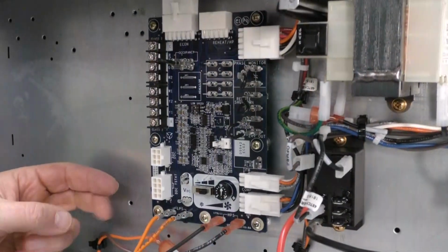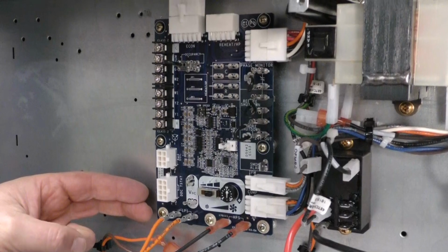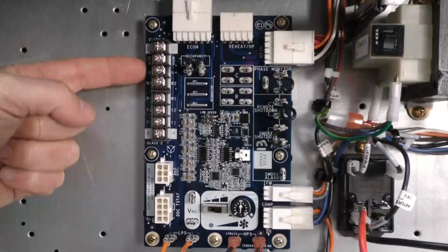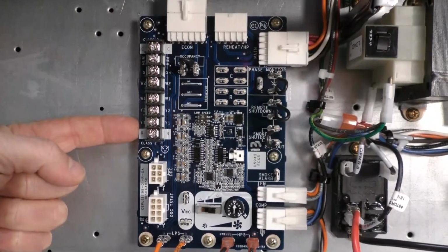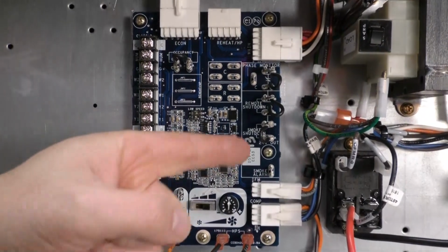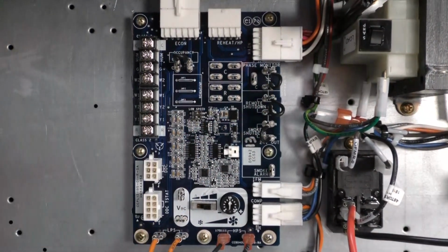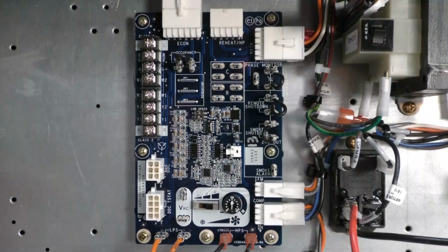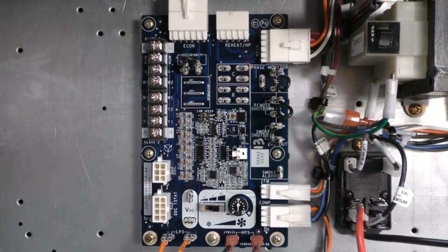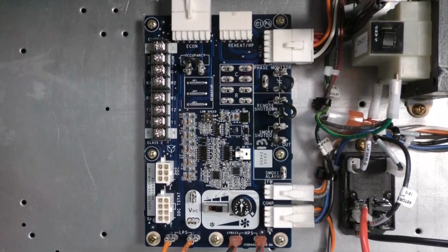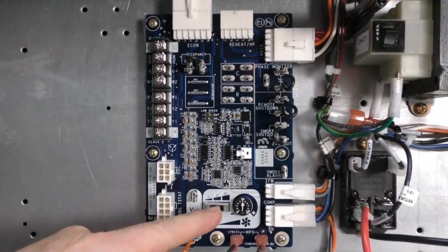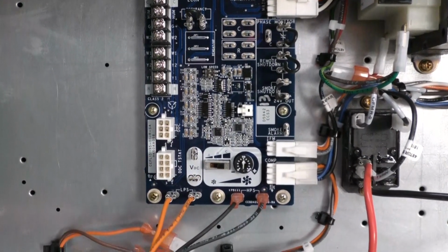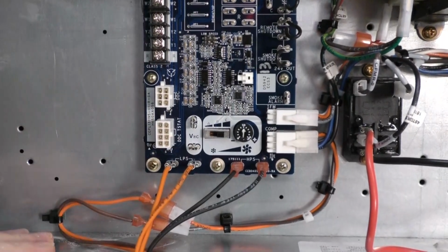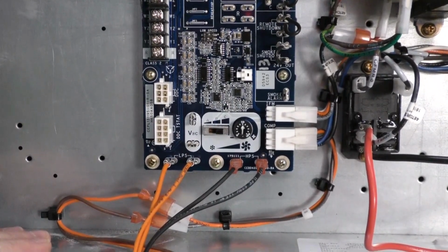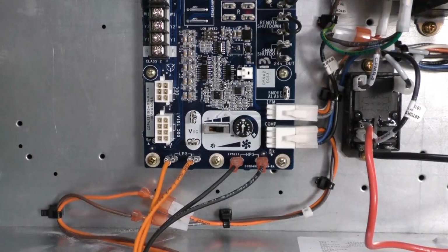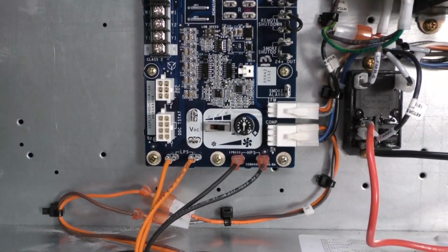This fan control board is not much different wiring-wise than the existing one. We've got our low voltage connection for a low voltage indoor thermostat, our jumper wire connections for things like occupancy control, smoke control. What is a little bit different about this particular board is the fact that at the lower portion of it, as we'll see later, there is a way that we're going to set up the airflow for the indoor fan. It's a different procedure, again, as reflected on the label on the outer panel.